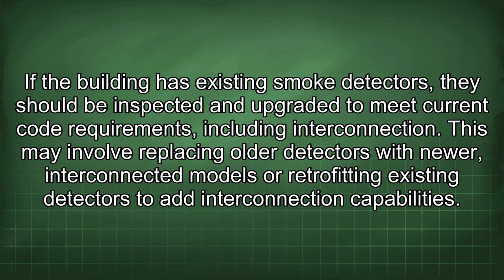If the building has existing smoke detectors, they should be inspected and upgraded to meet current code requirements, including interconnection. This may involve replacing older detectors with newer, interconnected models or retrofitting existing detectors to add interconnection capabilities.